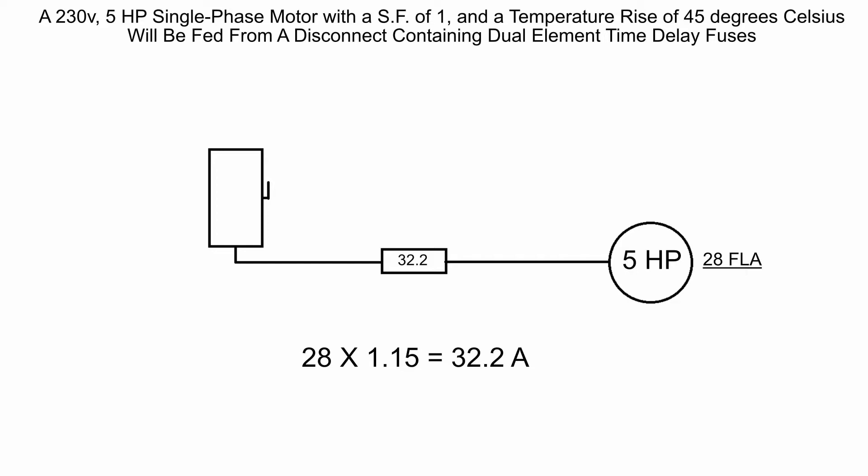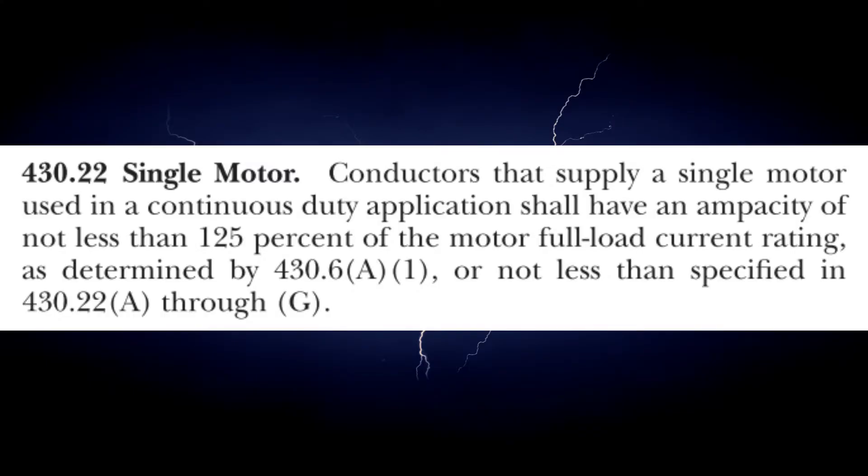To know how to do this we need to reference the code articles that are going to tell us that, and that's going to be 430.22 for a single motor. It says the conductors that supply a single motor used in a continuous duty application shall have an ampacity of not less than 125 percent of the motor full load current rating. Notice that it says continuous duty application, so what that means is it's a continuous duty application and that more or less applies to generally all motors.